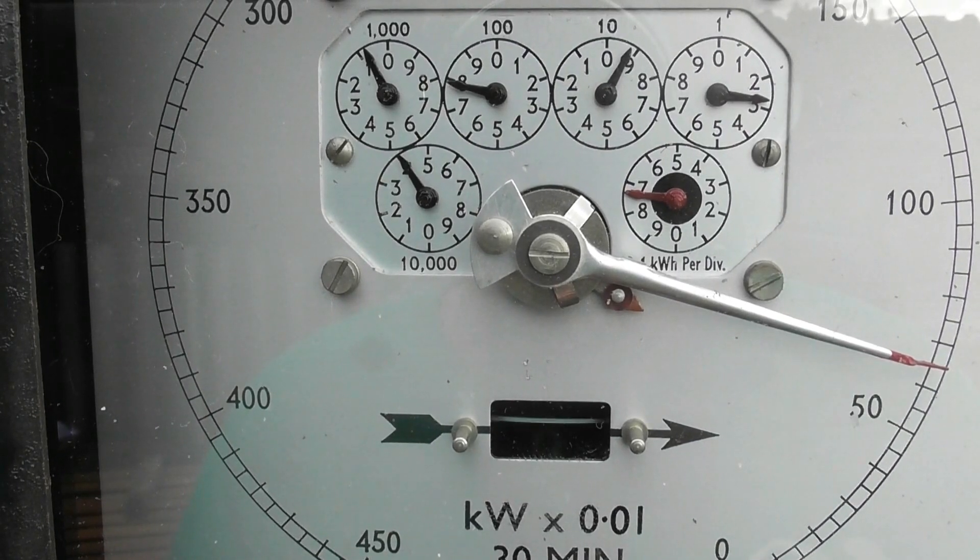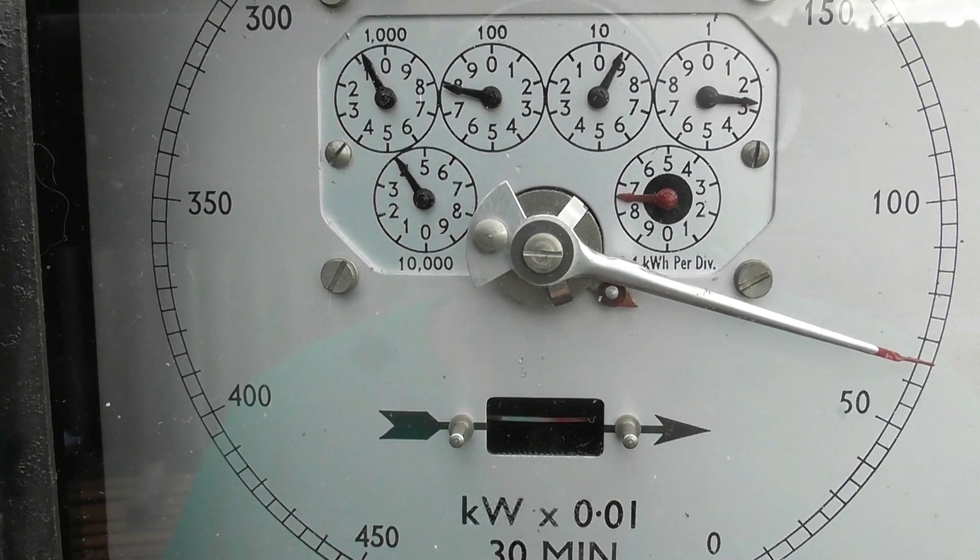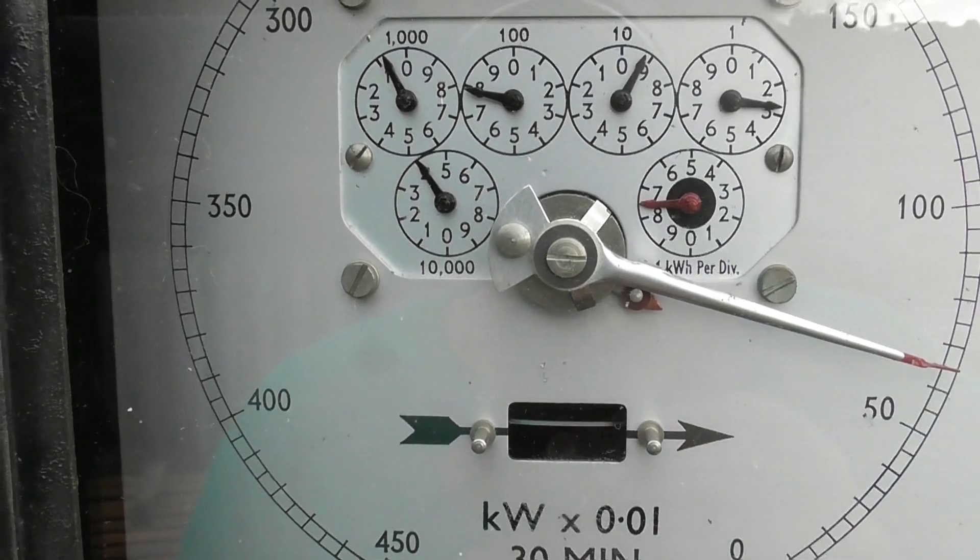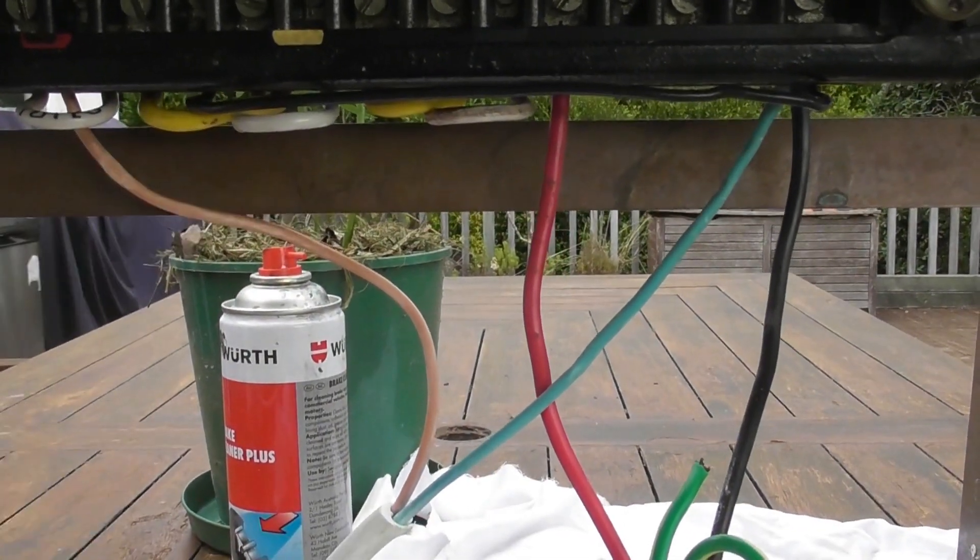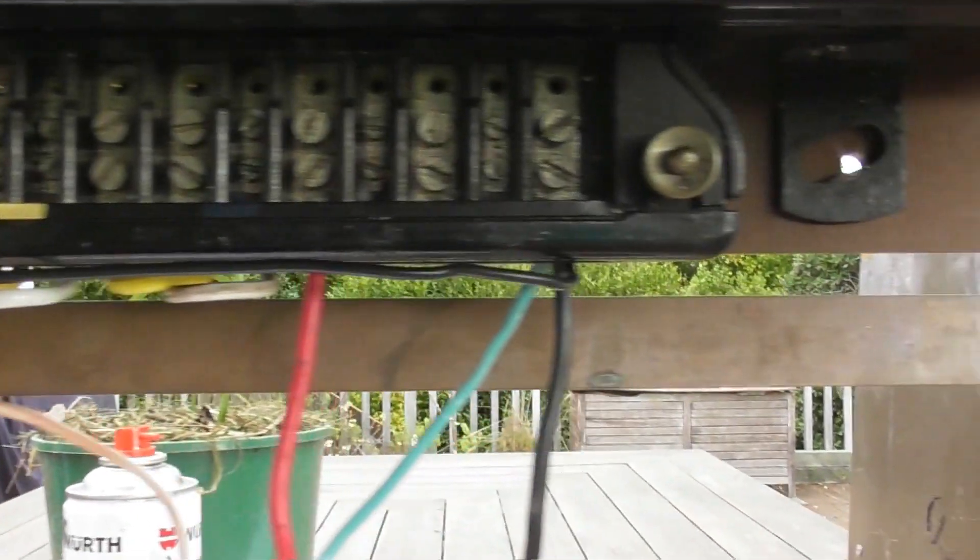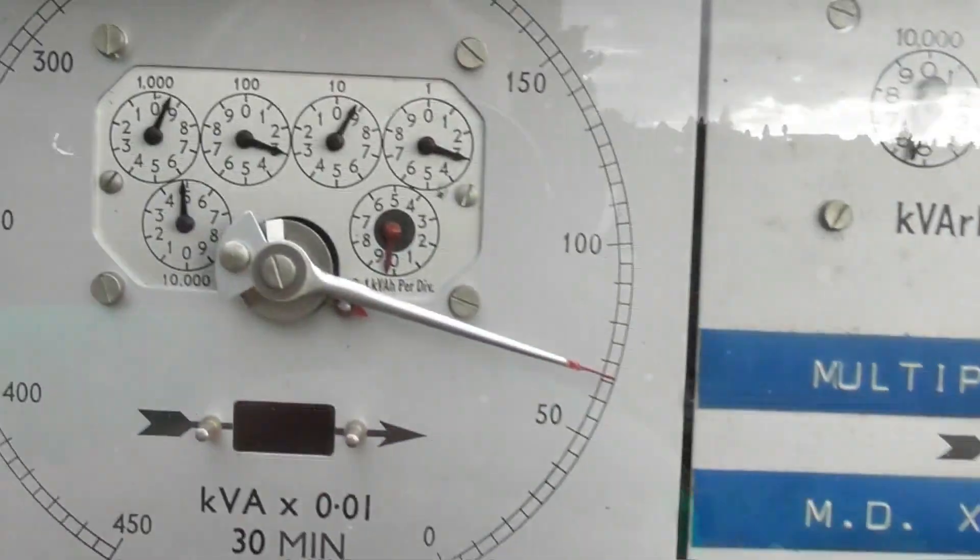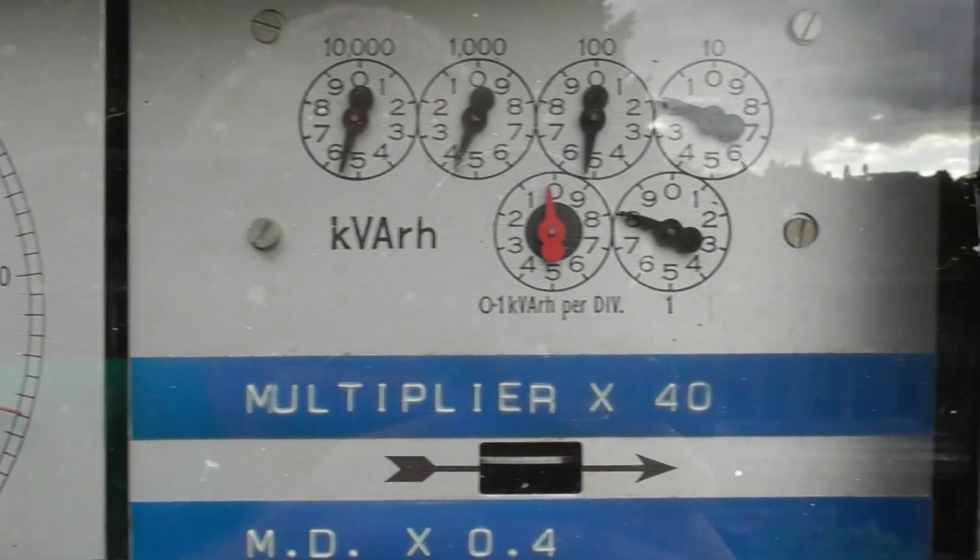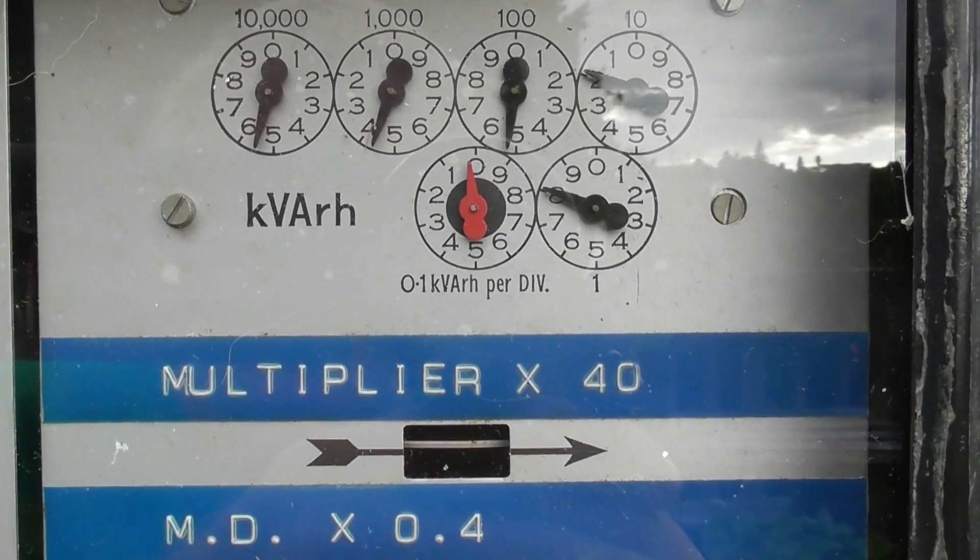I've got the repair done and the meter is running. The main spindle is still a bit bent because this thing has been dumped and it had some impact, but at the moment it's going fine. I've got the three elements wired in series, one kilowatt load on it, so it's about four and a half amps. The kVArh is going and it's advancing slowly, and there's a little bit of reactive power on here because this little blower fan in the heater causes a bit of reactive.